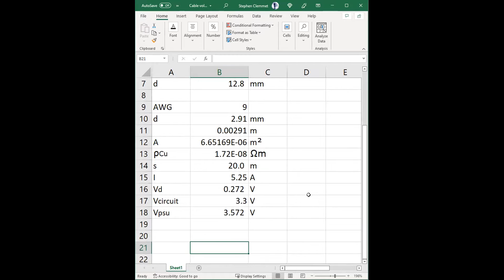So all I've done here is put into the equation my voltage drop, and if I enter all these magic numbers I can calculate what my voltage drop is. For example, let's say I've got a cross-sectional area of cable here of 2.9 millimeters, which is American wire gauge 9 I believe - we'll come to that in a moment. It'll calculate for us, based on the diameter, what the cross-sectional area is.